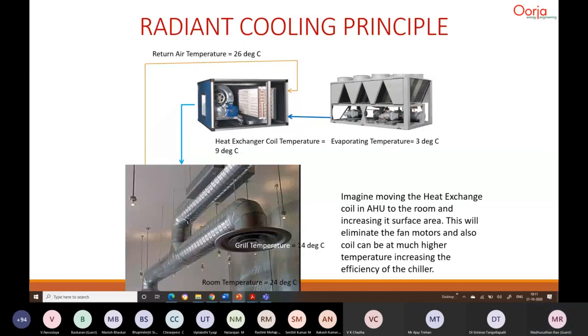But imagine if I were to pluck this heat exchanger from here and spread it all in the ceiling in all of these 10 classrooms, each of 1,000 square feet, what will happen? First, we will not require the fan motor, right? Because the heat exchanger itself is in the space now. We don't need to move air or hot air, or we don't need a heat exchange medium now. We don't require a heat exchange medium, so we can do away with this fan motor. So that is one connected load less.